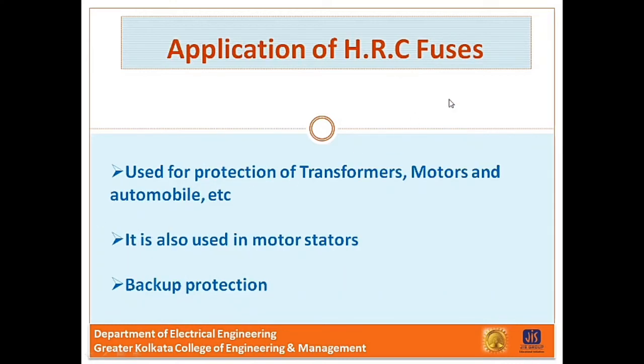Now what are the applications of HRC fuses? It's used for protection of transformer, motor and automobile. It is also used in motor starter and it is used as a backup protection. HRC fuses for low voltage installation is easily replaced. And HRC fuses provide high speed operation in short circuit and overcurrent protection. So they also provide stability in industrial power distribution and semiconductor protection.